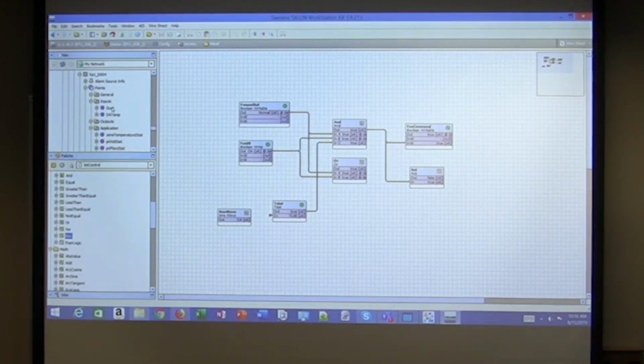So the whole idea about the JACE is it's a normalizer to pull in multiple protocols and make them fit into three categories, or four, right? Boolean, numeric, enum, or a string object. And that's the whole purpose of the JACE, to be able to normalize it. So if I'm looking at a graphic, I don't know whether it's a VAV Smart 2 card, a LON card, or a BACnet card. Could be any of those underneath the graphics. I don't really care. I'm just trying to get information, right? And make that stuff work.